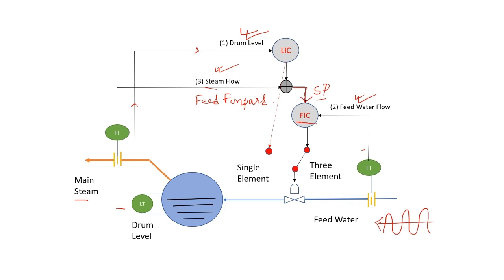But can this three element drum level control be used throughout the process of the boiler? No, because when the boiler starts up, the flow of the main steam and the feed water flow both are insignificant.